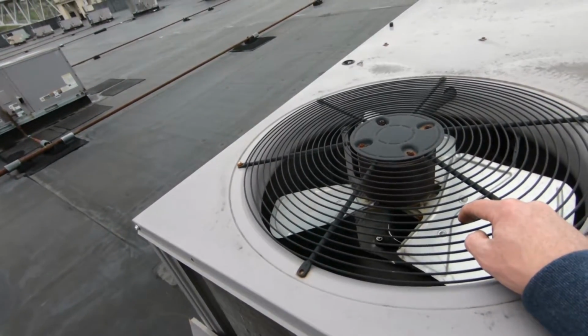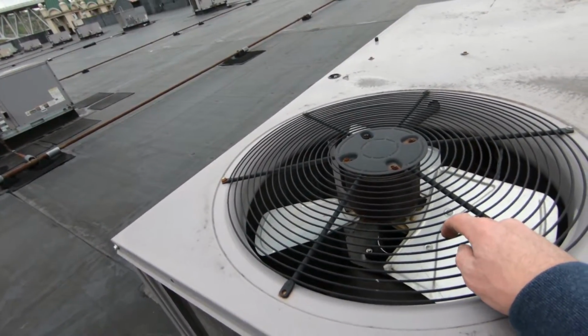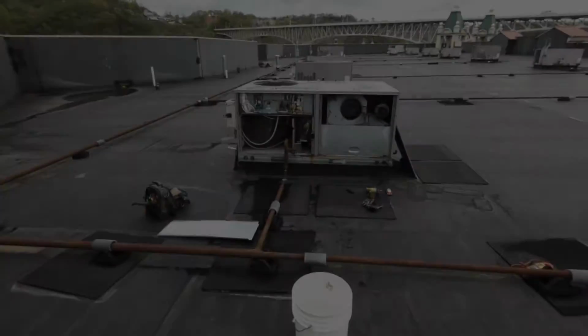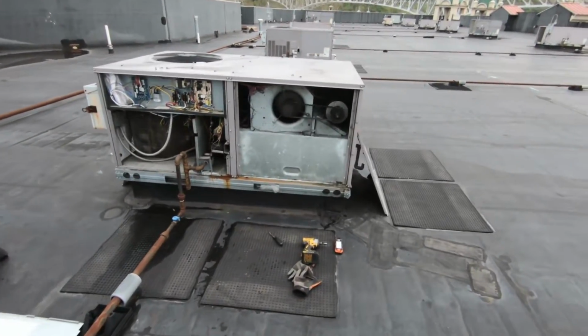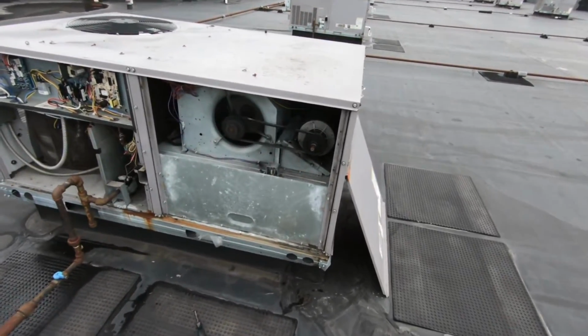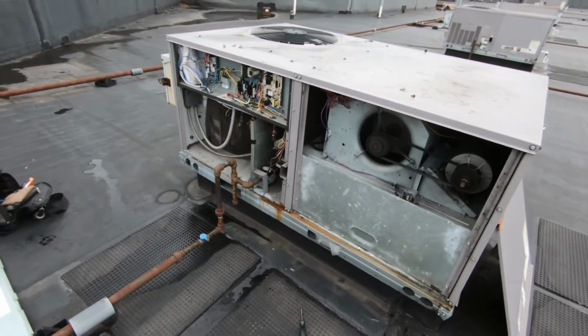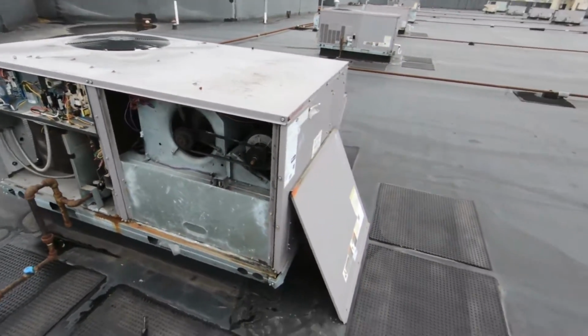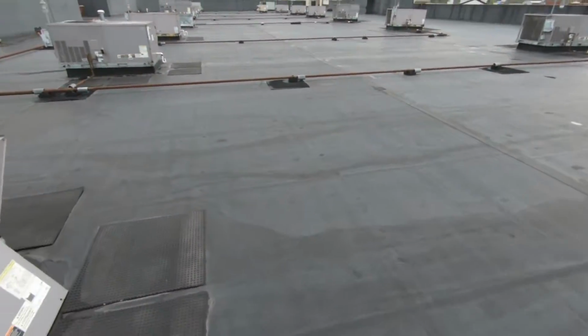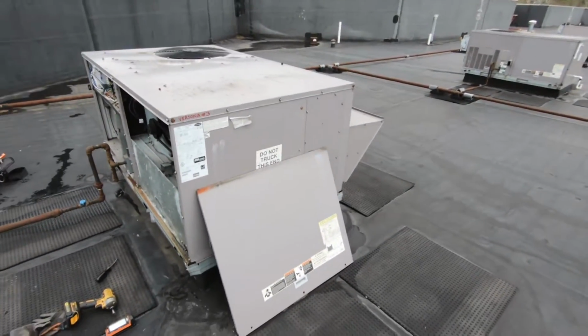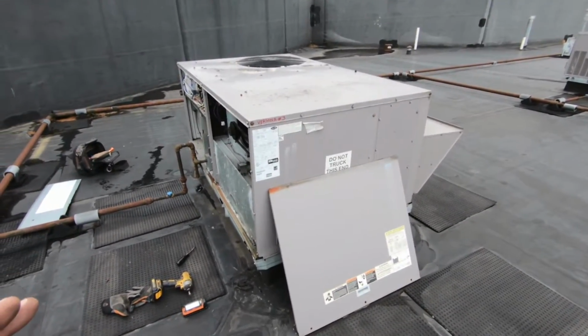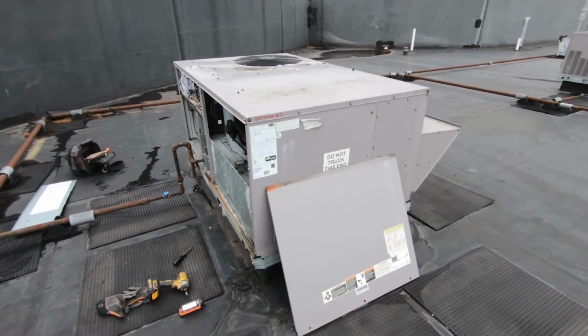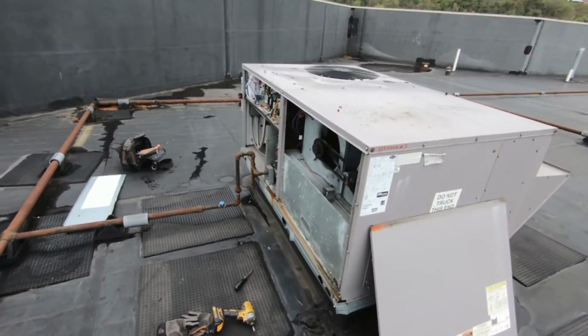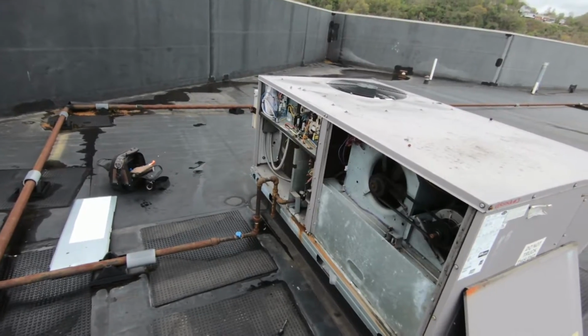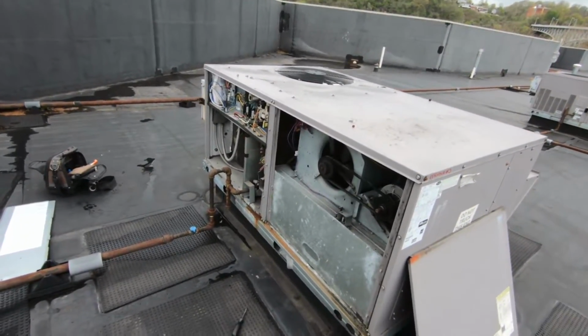I'm gonna head down to the mechanical room now, and I'm gonna reapply power. A few moments later. All right, I got power back on to number 3. Blower's running, needs a belt of course. I pushed in the contactor for the compressor. It didn't blow anything. So I'm gonna go ahead, I'm gonna cycle it in heat just to make sure that gas valve works. If not, then we'll write up a new gas valve when we replace the heat exchanger. And I'm gonna run the air conditioner, make sure it's good to go.